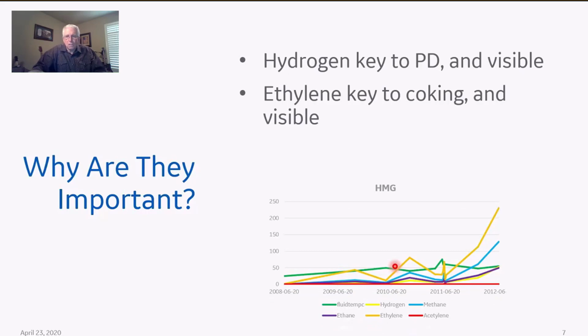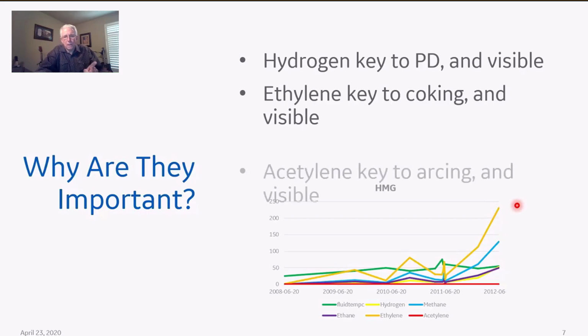Ethylene really is the key to coking. I'll pull up this diagnostic graph of these gases and the fluid temp as well. You can see some fluid temp increase here periodically, but if you look at what's actually being generated, here's hydrogen right down here next to ethane - I think that's ethane below it - so they're kind of running hand in hand. If you look at the main generator here, it's ethylene, and you can see ethylene has really begun to take off.